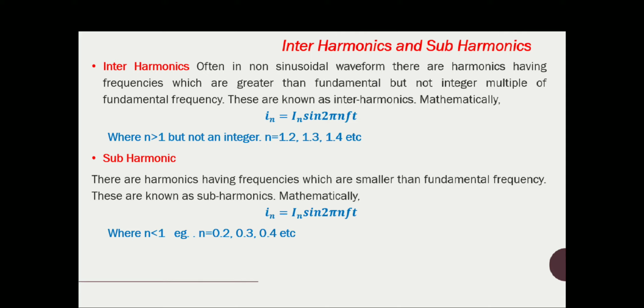So when n is greater than 1 but not an integer, such as n equal to 1.2, 1.3, 1.4, etc., for example I sine of 2 pi times 1.2 f t, that component is known as interharmonic. But what happens if n is less than 1? Then it is known as subharmonics - harmonics having frequencies smaller than the fundamental frequency. If the fundamental frequency is order 1, and the order is less than 1, like 0.2, 0.3, 0.4, etc., then it is known as subharmonics. So understand the concept: interharmonics is n greater than 1 but not an integer, and subharmonics is n less than 1.